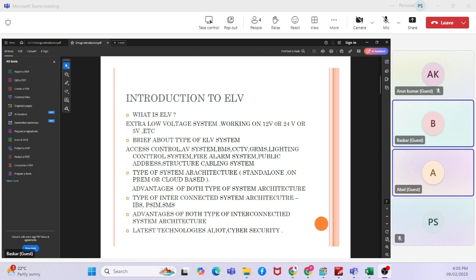Yes, thank you. So the evacuation procedure or the life safety system, the fire alarm system supplier or the client, will define which doors are fail safe and fail secure. It's not defined by the ELV solution provider. It's defined by the consultant. The consultant will give those doors, and it has to be configured. Wherever the fail safe doors are, there will be a fire alarm interposing relay. That fire alarm interposing relay has to be connected with the access control system to activate and open the doors.